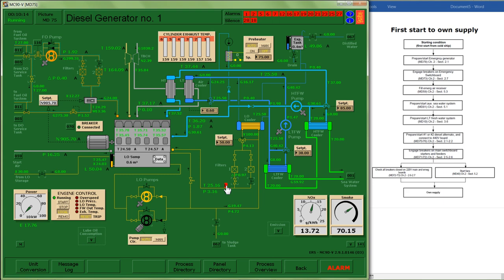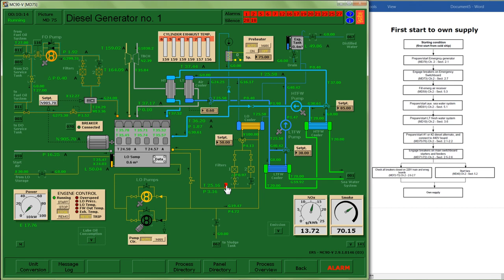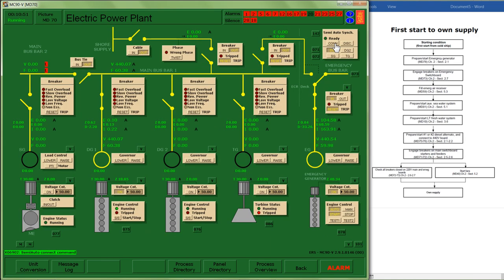I'm going to jump ahead and connect it under load. Once again, I would want to make sure that all of my parameters are in the normal operating range before I put this generator under load. My DG1 is running. The generator is producing 440 volts. It looks like it's suitable to connect to the main bus. I'm going to use semi-auto synchronization for that, so DG1 tells me it's ready, and I will connect. My breaker has connected.